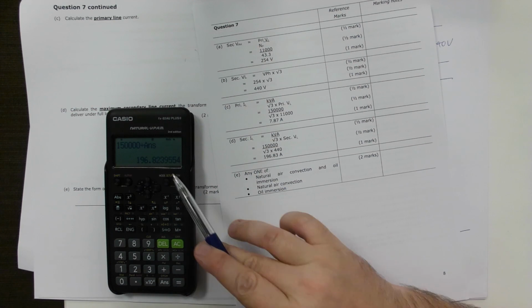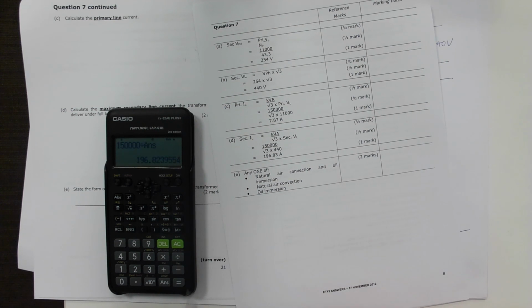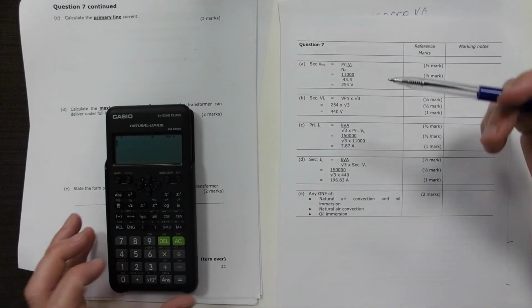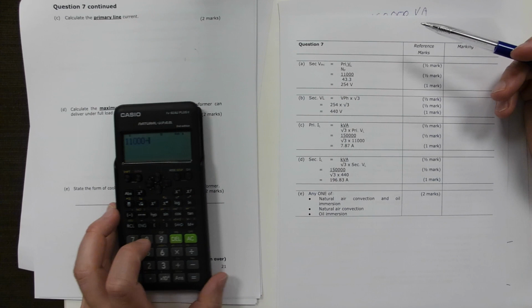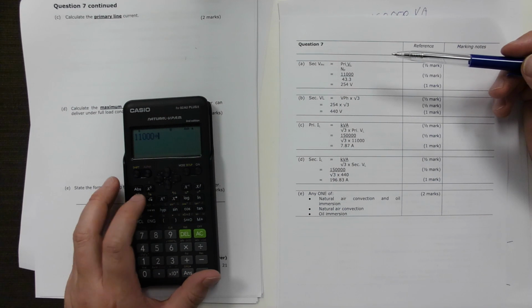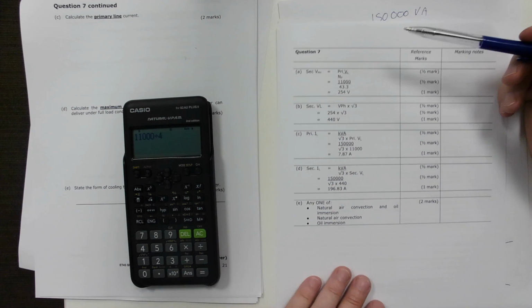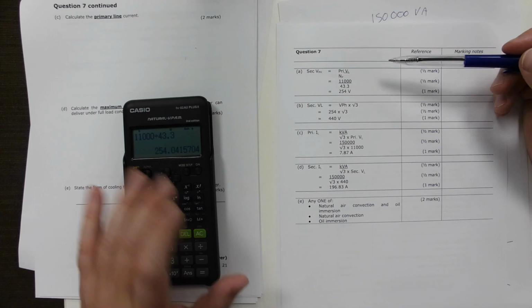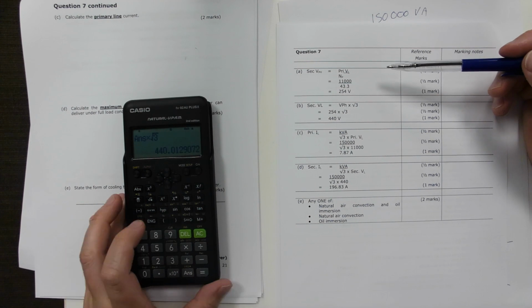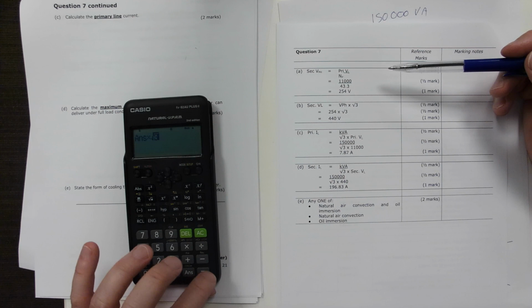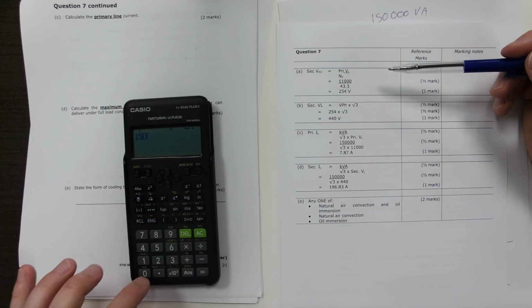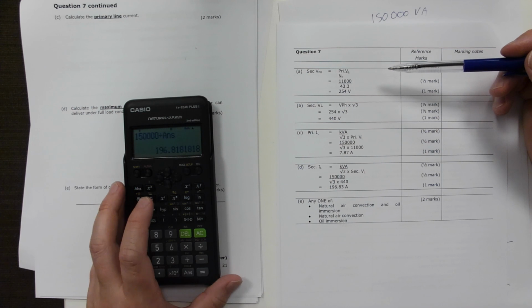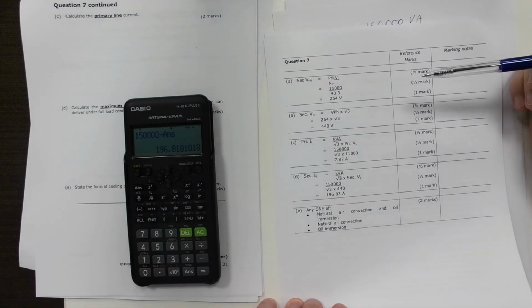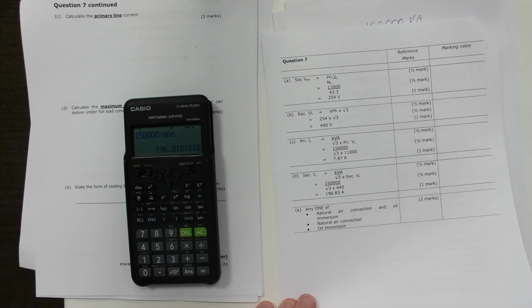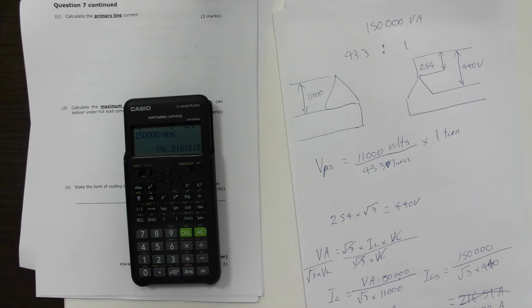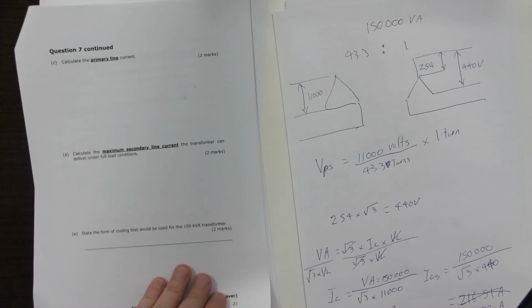So curious where they get that from. It might be if I change that 440 to more accurate, so 11,000 divided by the 43.3, because we did round in this question. It's giving us our voltage there. Then we times that by the square root of 3 to get our line voltage. And then we times that by the square root of 3 again, get 150,000 divided by our answer, and we get 196.81. So they've actually rounded the wrong way. Good to know. And I believe that's the end of that question.